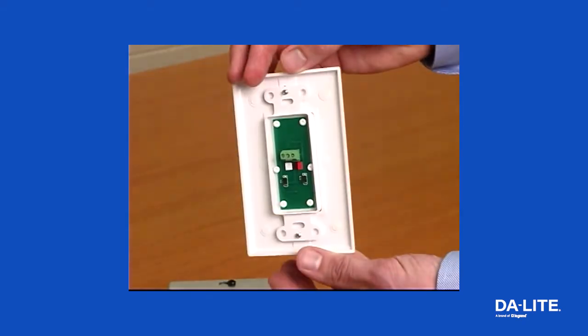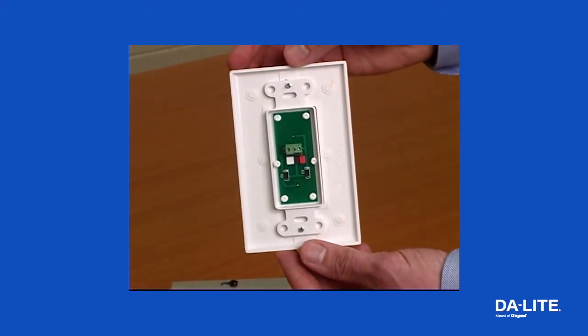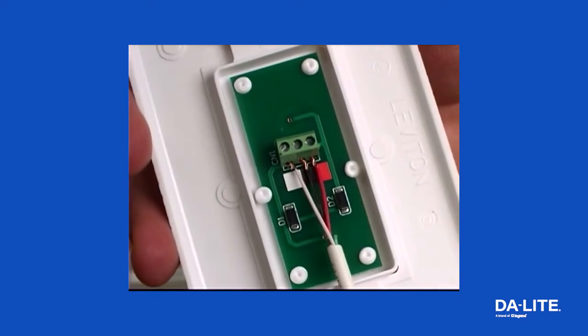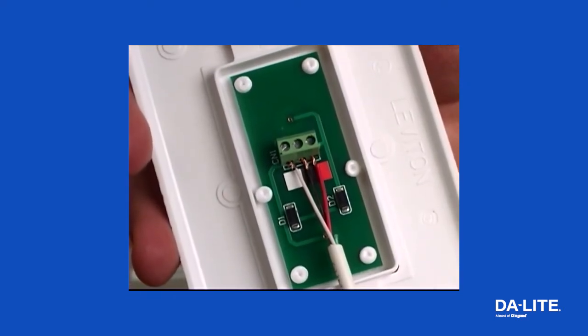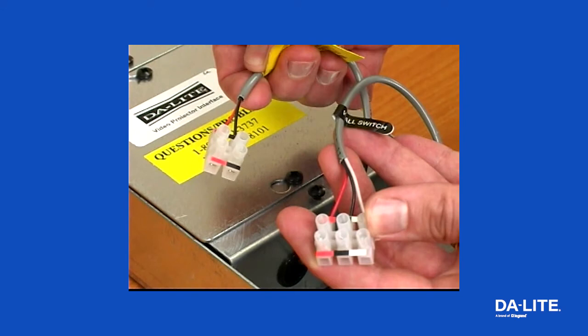When connecting the supplied low voltage wall switch, use three conductor 20 to 24 gauge wire to extend the switch to the required length. Connect the wire from the switch to the wire labeled wall switch. Never apply voltage to the wall switch lead or the VPI will be damaged.